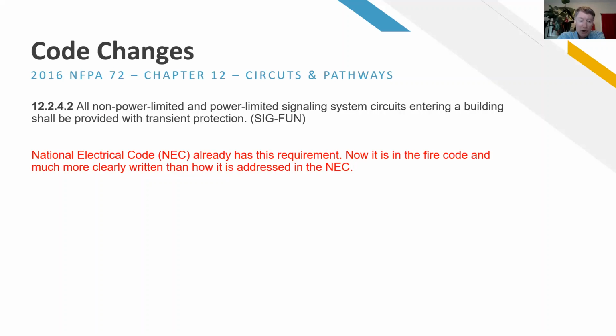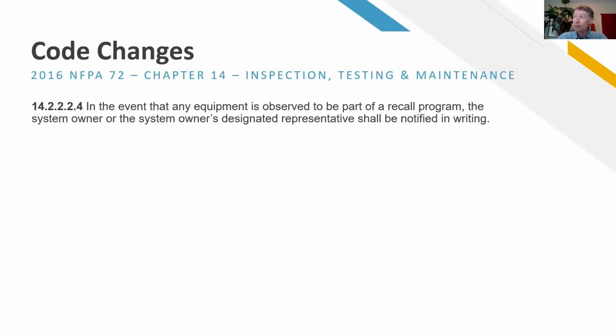Yeah, and Mark, just in my experience, it's those PIV valves. If you have a lot of post indicator valves outside or by the parking lot, where you can shut off manually all of the water into your building, the fire alarm system needs to monitor that. And if they're ever hit by lightning, it can travel down a pretty long length of conduit and fry everything attached to that. So if anyone has buildings with PIV valves, I would ask your fire alarm contractor to check and see if you have these installed, and if not, you might want to think about doing that, just as risk mitigation.